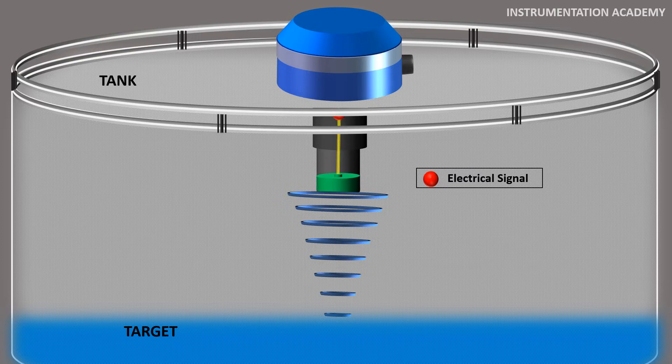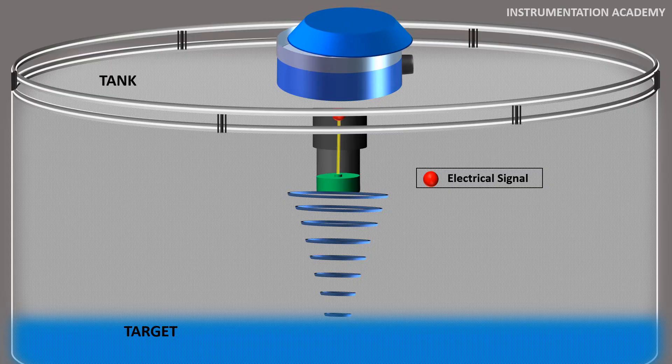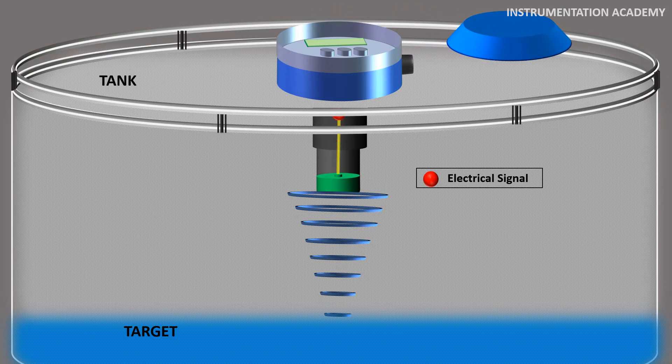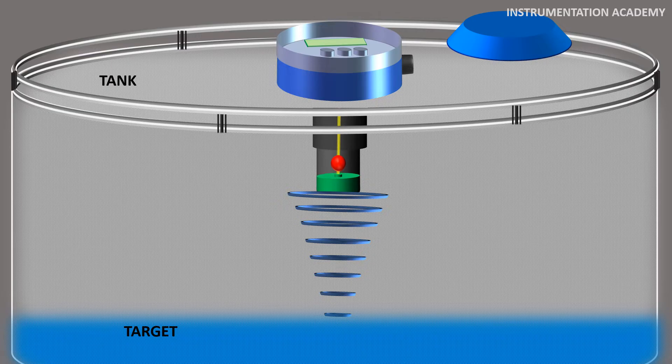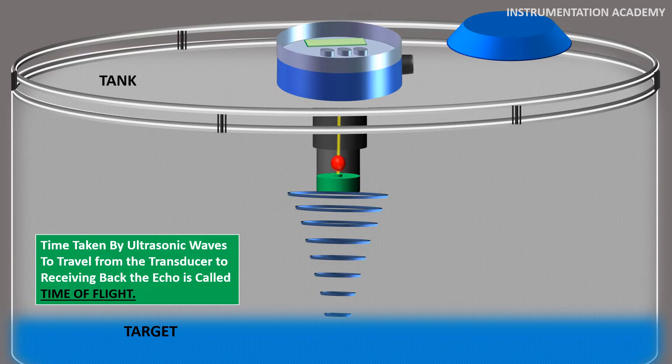An electronic signal processor analyzes the returned echo and makes sure that these echoes are from the target and not from walls, beams, pipes or any other obstacles. Now it calculates the time taken by the ultrasonic waves from leaving the transducer to receiving back the echo. This time is known as time of flight.